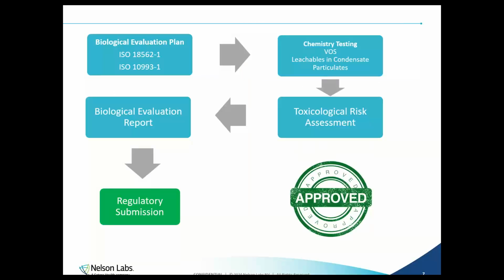In the regulatory pathway, from the first initial conception steps, the biological evaluation, to regulatory submission, these standards would more than likely follow in this order. A strong BEP should be authored. It follows guidance from 18562-1 and 10993-1.